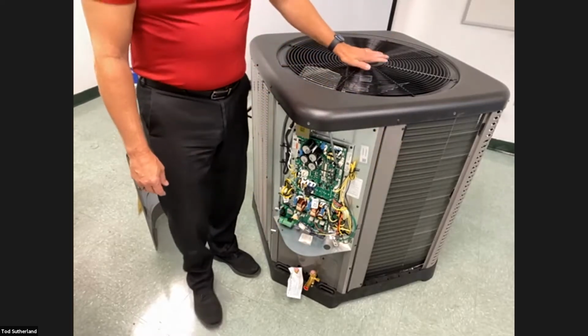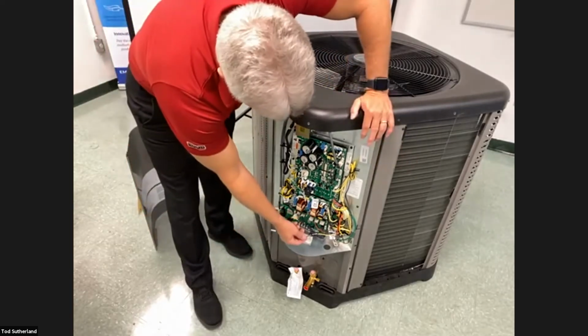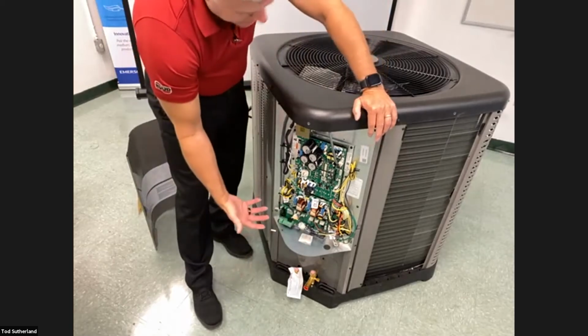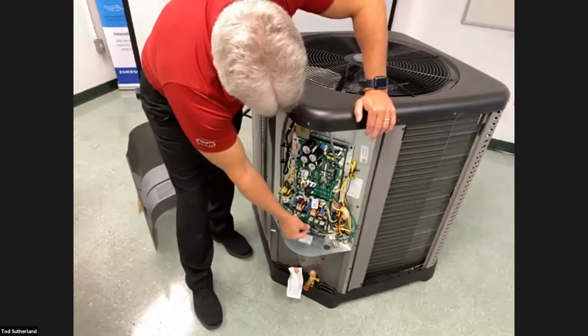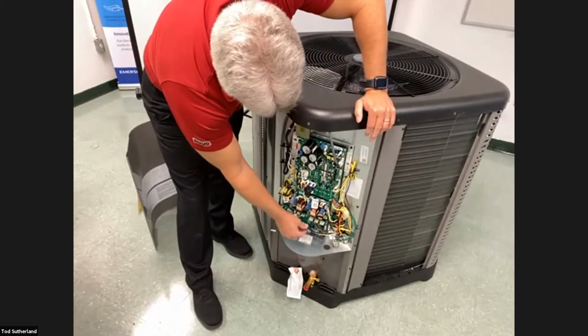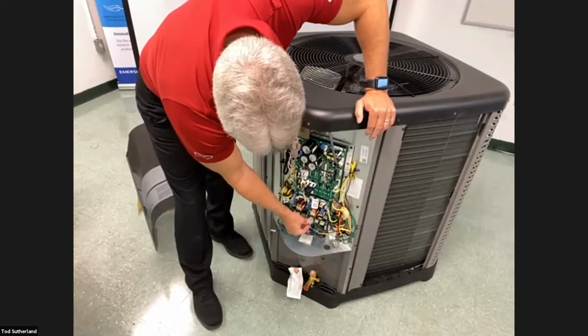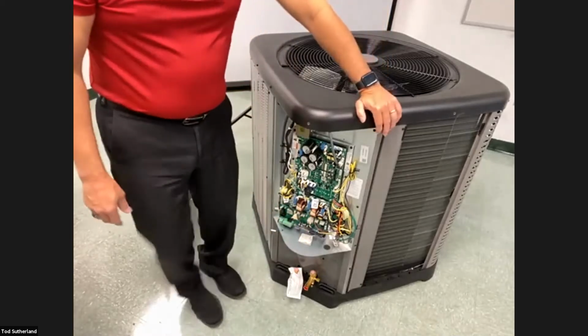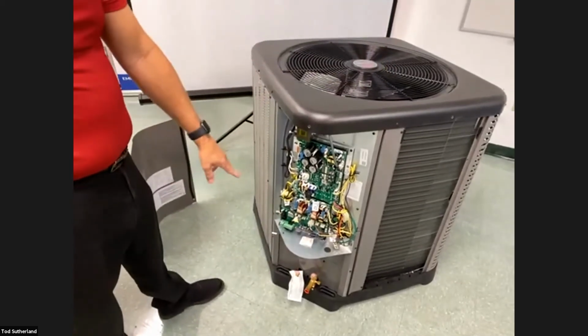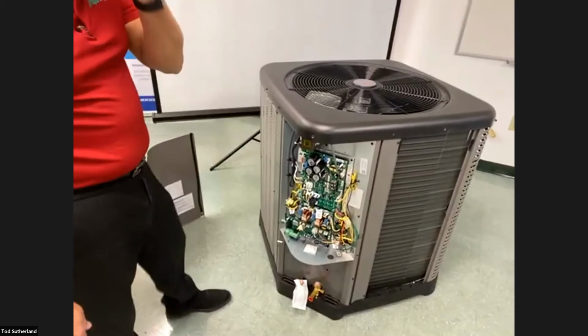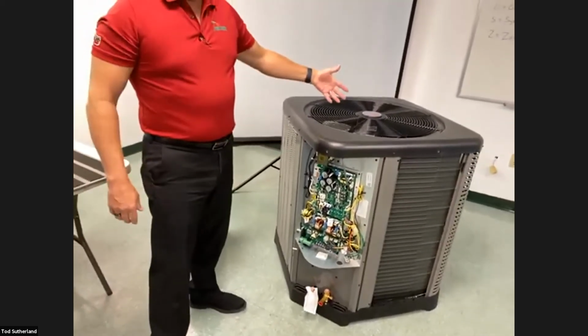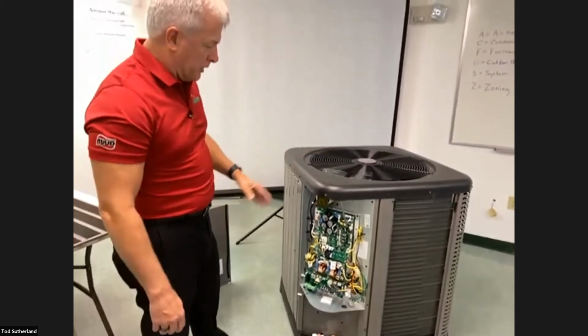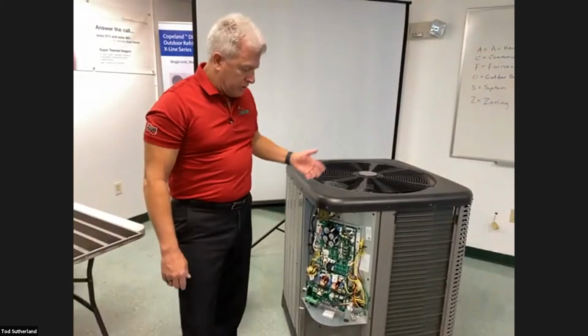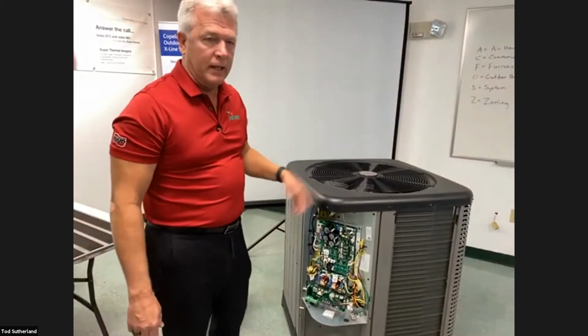If the fan does not run when you jumper that, then you're going to have to dig a little bit deeper. It would either be in this wiring or in this board, and you'd need to replace either or. But you can apply 24 volts directly to that plug, and your fan motor should spin. Now the board controls that, of course, so you don't want to just jump it and leave it like that.